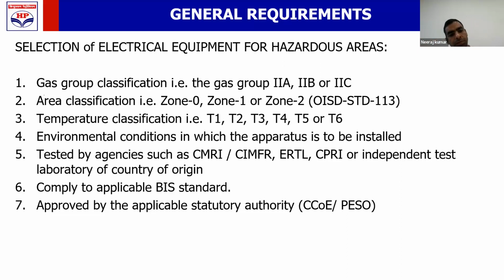You should also see that the electrical equipment you are choosing, as per temperature class, gas group, and zone, should also have the relevant laboratory test certificate and approval by CCOE or PESO. Both are the same thing. So test certificate, PESO approval, suitability for temperature class, suitability for zone, and suitability for the gas group. In addition to them, compliance to BIS, which is anyway there. So while selecting electrical equipment for a hazardous area, these 7 things should be seen.